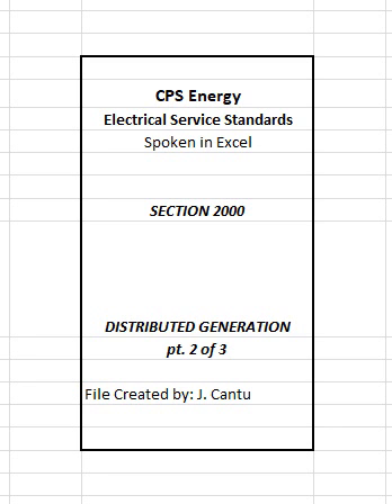2. Line and load conductors must be identified at their terminations. Meter loops lacking properly identified conductors will not receive a CPS Energy meter. Customer assumes all responsibility for conductors that are improperly identified or terminated. 3. Meter sockets must have the line side (PV source) conductors connected to the line side (top) of the meter socket. Load side conductors must connect to the load side (bottom) of the meter socket. Refer to Figures 2002 and 2004.